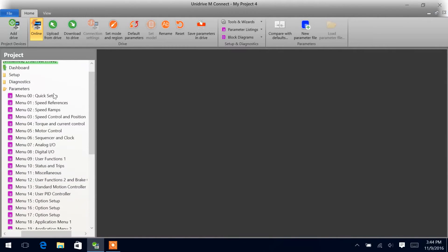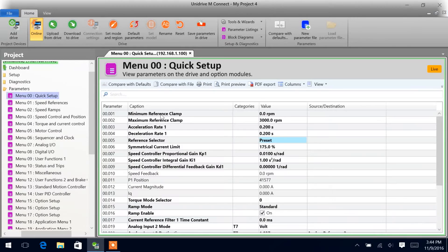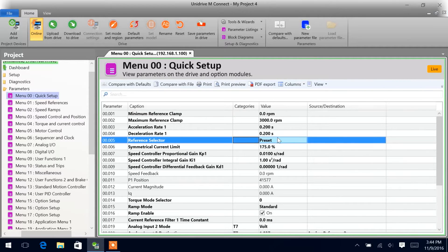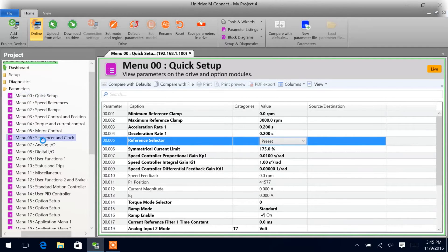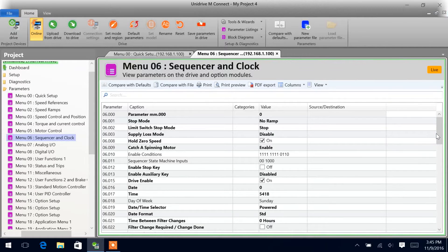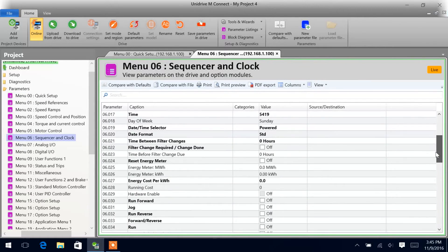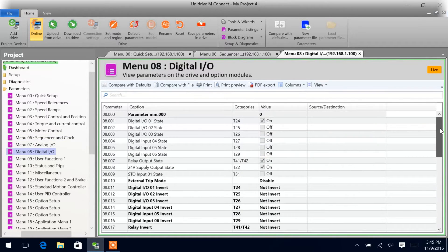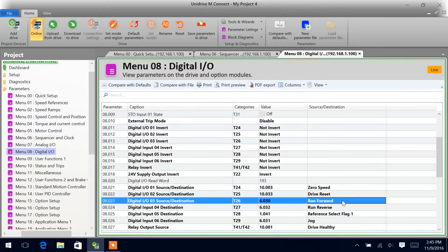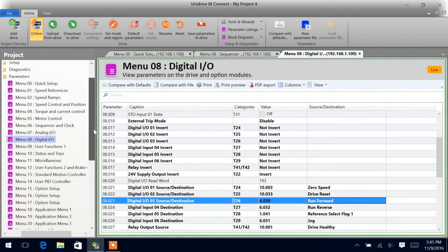We're going to start in menu zero and make sure the reference selector is set up for preset. We'll also want to make sure that we have a way to trigger the run forward — menu six, parameter 30. The way we're going to do it is using digital IO three, which is default set up for 6-30, so we'll leave that as is and use the digital input.